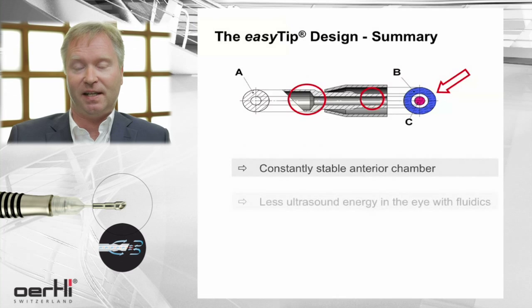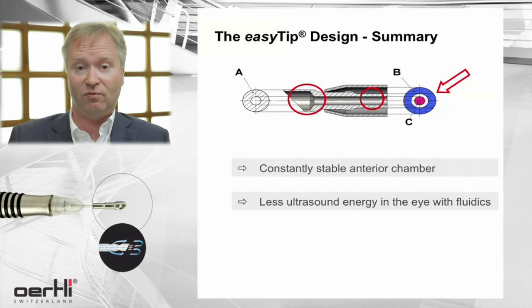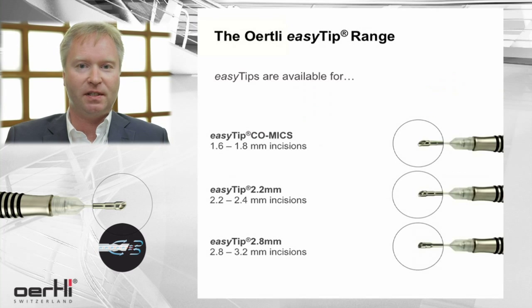You have less ultrasound energy to be applied as fluidics is working for you. Fluidics is responsible for the very high followability of fragments as well as for the holdability, and that gives you the chance of very good energy coupling. So in the end, you are saving ultrasound energy. EasyTip technology is available in three different incision sizes.